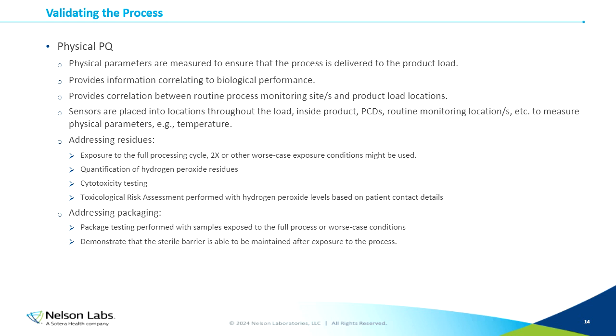We also, as part of the validation process, need to address packaging. Packaging is an important component, and it's something that maintains our sterile condition after exposure. So package testing is performed with samples exposed to at least the full process. We may choose worst case conditions, as was mentioned above. We might say that we want to expose to 2x processing, or we decide that there's another worst case condition that we want to consider for that testing. We demonstrate with those exposed samples that the sterile barrier is able to be maintained after exposure to the process.